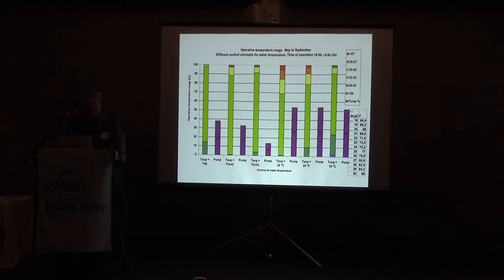But we see here, if you have the maximum cooling, here you have the running time of the pump, but it really gets too cold sometimes. We have 15% where it's lower than 22 degrees. And that would often be too cold for many people in summertime. Then if we control according to external temperature in different ways, we can really reduce the pump running time, and the comfort is not worse. We may now get up to 26 degrees. But most of the time we are in the comfort range.